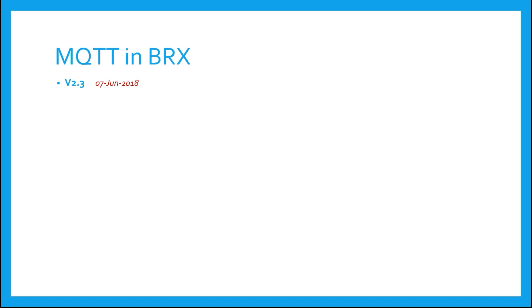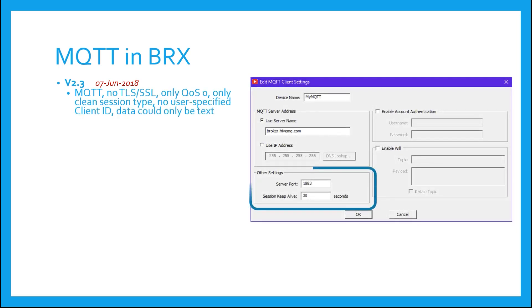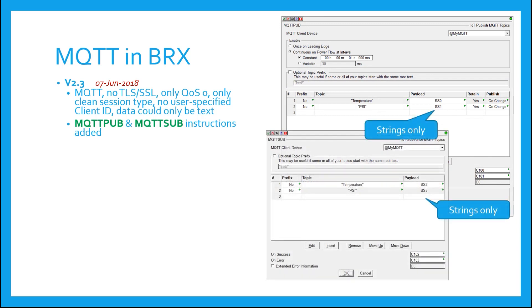MQTT was introduced in Do More Technology version 2.3 in June of 2018. It had no TLS or SSL encryption support, only supported a QoS of 0, only a Clean Session Type was allowed, there was no user-specified client ID allowed, and the only data you could publish was text. Whatever was subscribed to was stored in text in the BRX, meaning if the data you needed was a numeric, you had to use other Do More instructions to convert it from a string to a numeric. The MQTT PUB and MQTT SUB instructions were also added to facilitate using MQTT in a BRX PLC.